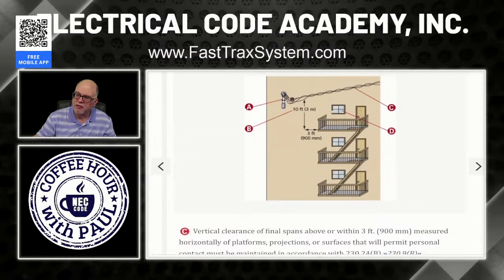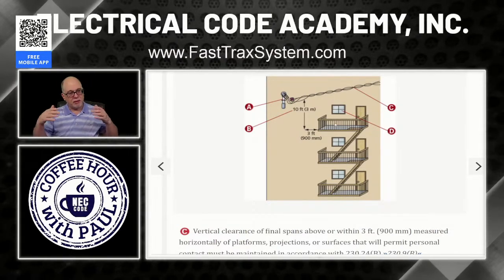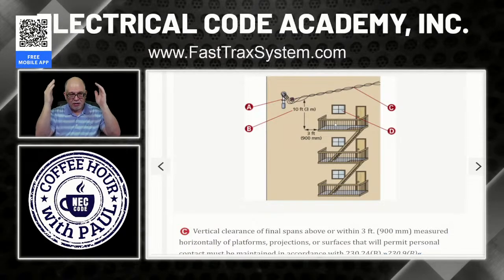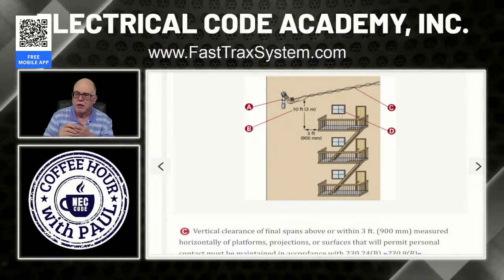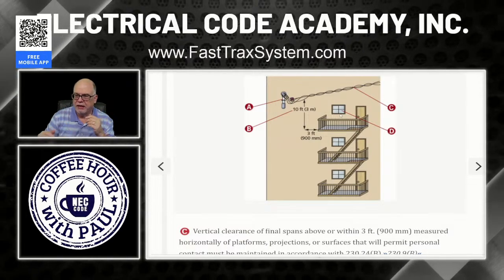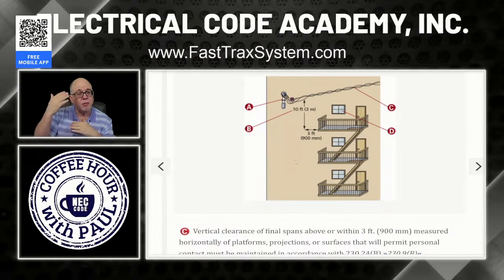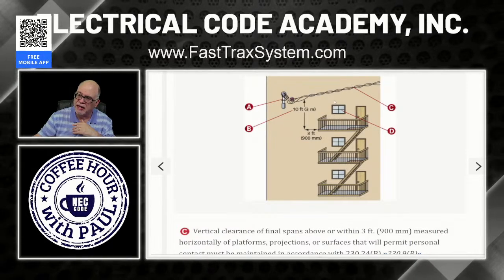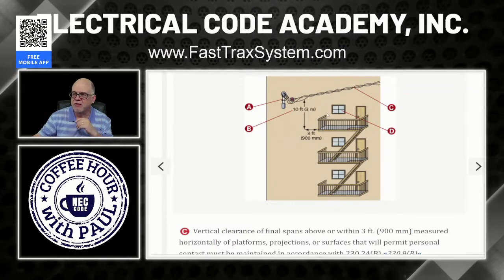Okay, so just because the window doesn't come into play above it, it still needs to be high enough because the platform is accessible to pedestrians. They can get there. So we still have to have the 10-foot clearance above it. Okay, see how all that works together? You have to be very aware of your situation, right? Now, if none of this was here, then these conductors would only have to be, what, 10 feet from grade. But because of these platforms and people standing out here on it, it could be accessible. So it has to be 10 feet above. Makes sense? All right.